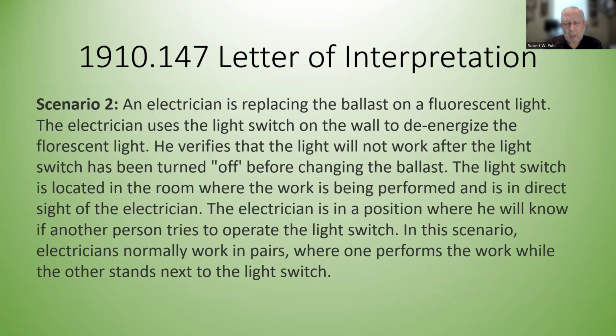So I guess they said it was 5 feet away. So like you said, there wasn't enough information there to give a definitive answer. All right, another one. An electrician is replacing the ballast on a fluorescent light. The electrician uses the light switch on the wall to de-energize the fluorescent light. He verifies that the light will not work after the light switch has been turned off before changing the ballast.